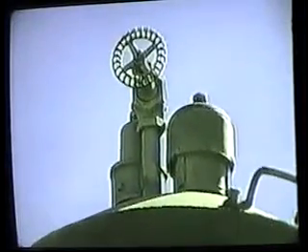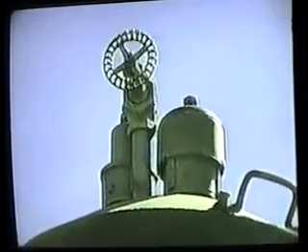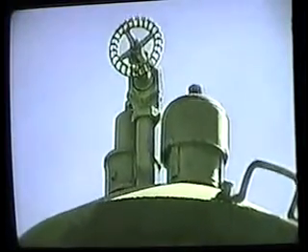You want these valves to lift when you're first steaming up in the morning to make sure that they are operating properly. Under normal circumstances, you want these to lift as little as possible, as the popping of these valves wastes approximately 2 gallons of fuel oil a minute.